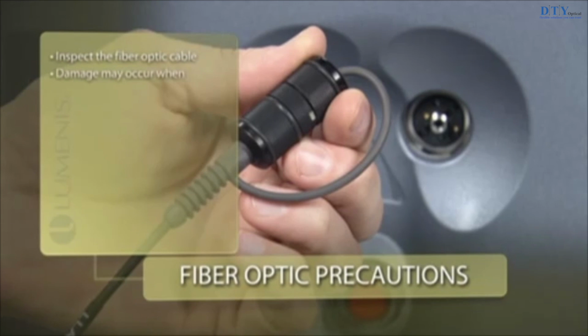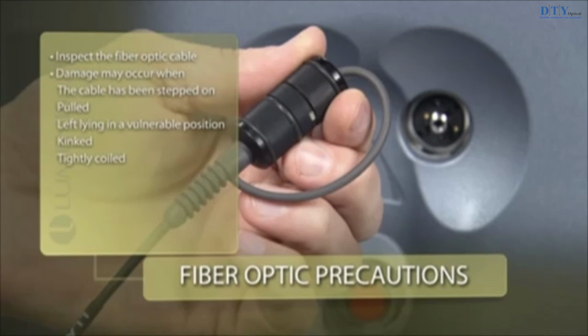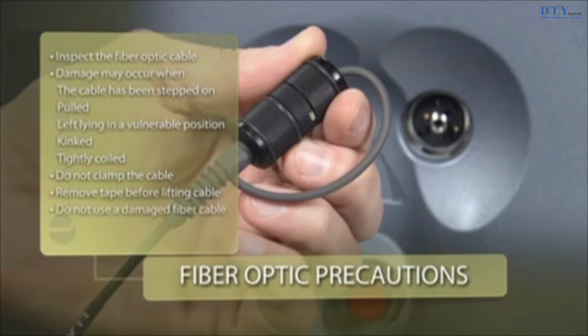The fiber optic cable may be damaged if stepped on, pulled, left lying in a vulnerable position, kinked or tightly coiled. Do not clamp the cable with a hemostat or other instruments. If sterile tape is used, always remove the tape before lifting the cable. A damaged fiber optic cable may cause accidental laser exposure or injury to the treatment room, personnel, or patient.